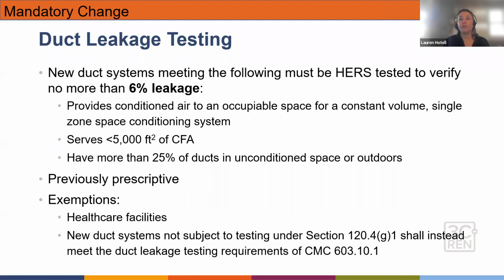Duct leakage testing is a new change for us. New duct systems must be HERS tested to verify no more than 6% leakage, as long as they apply under the bullet points: providing conditioned air to an occupiable space, serving less than 5,000 square feet of conditioned floor area, and having more than 25% of ducts in unconditioned space or outdoors. This was previously a prescriptive requirement. Under 2022, it's now required. New duct systems that are exempt from the mandatory requirements are new for this code cycle, including the exemptions below. Healthcare facilities and new duct systems that are not subject to testing instead need to meet the duct leakage testing requirements of the code listed on the screen.